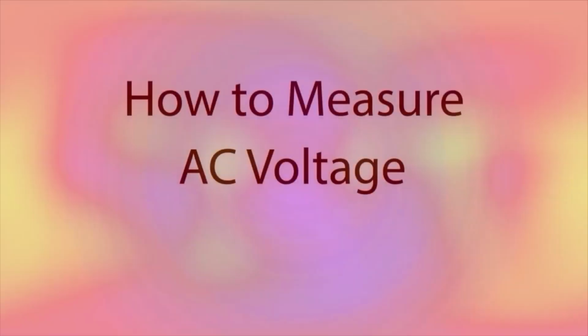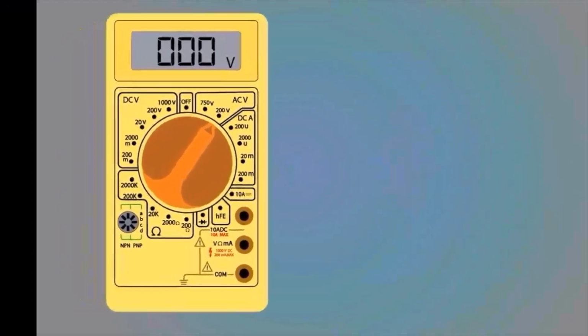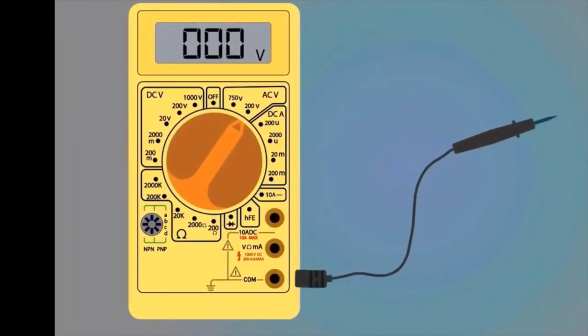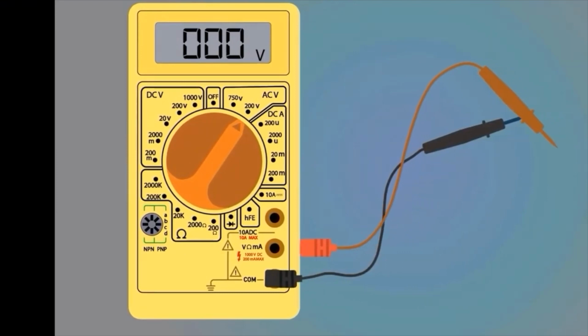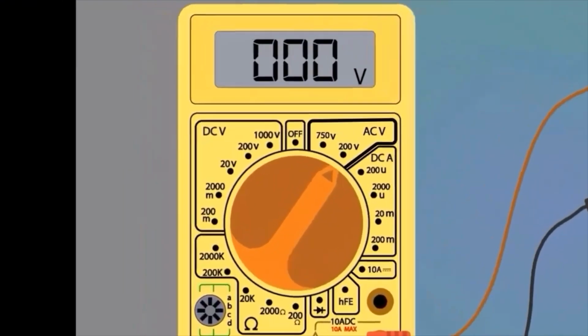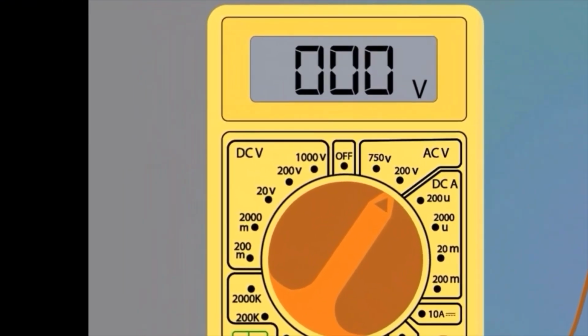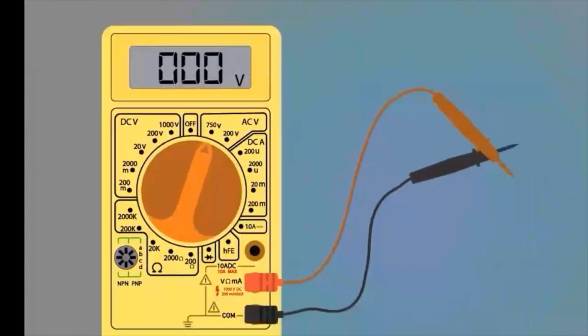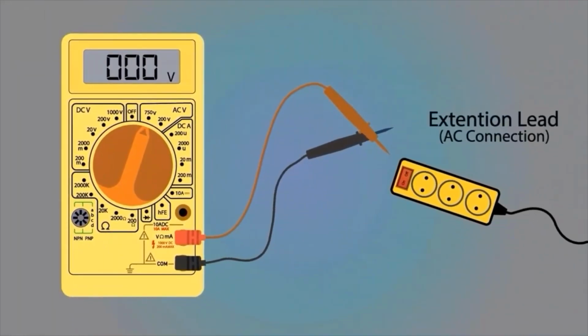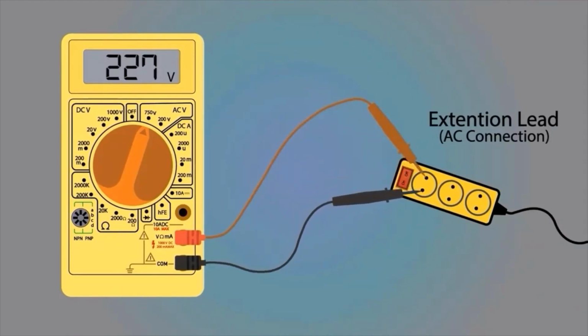Now we will see how to measure AC voltage with the help of a multimeter. Connect the black probe here and the red probe here. The blinking line shows the AC voltage section and the arrow shows the voltage range we can measure. Select the 750 volts range. Take an AC connection to measure AC voltage. Put probes into the extension lead connection. The multimeter is showing 227 volts. This is how we can measure AC voltage.